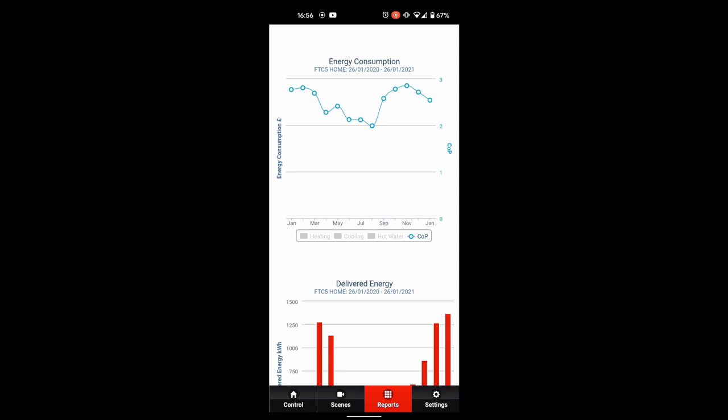And that's showing me my coefficient of performance. So you can see here we're ranging between 2 and up to 3. It's to do with Max's system. Here he's using radiators and he's running at quite a high flow temperature for this example, just to help my figures.